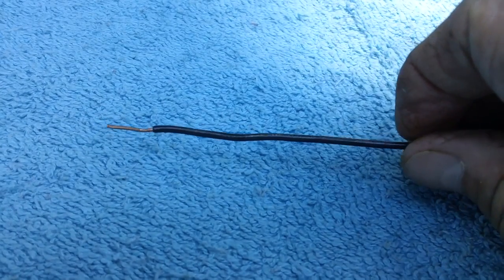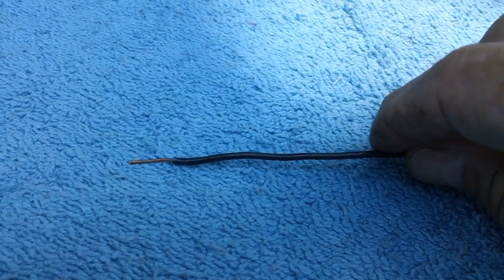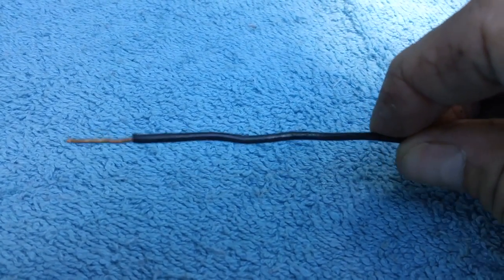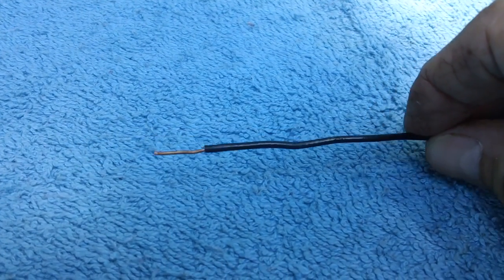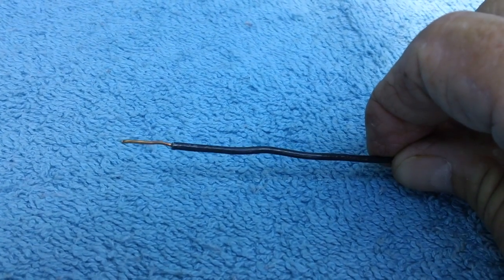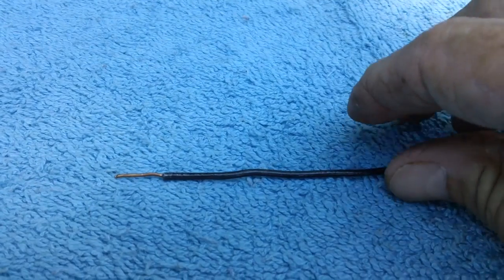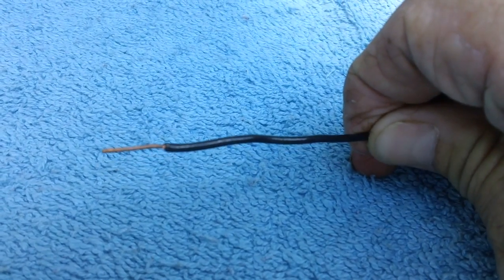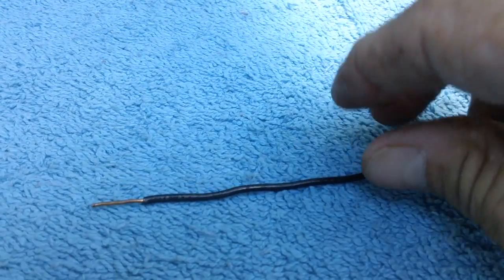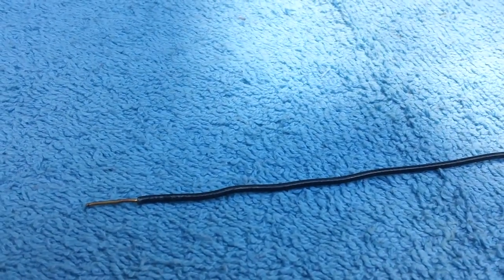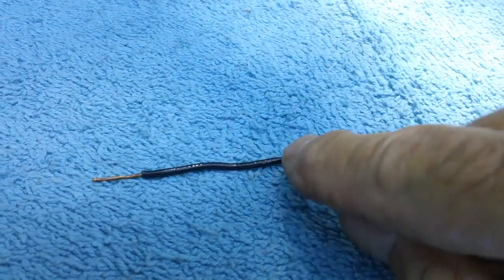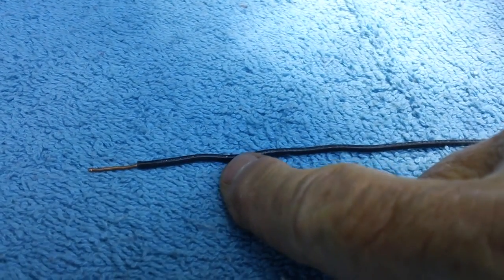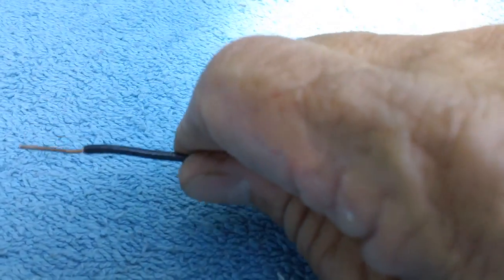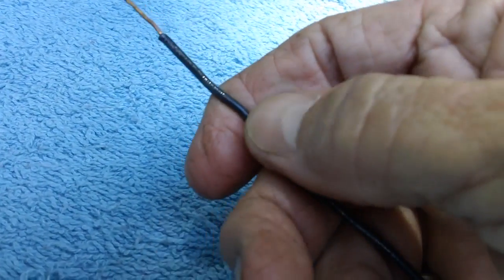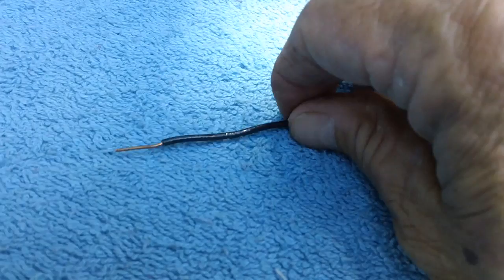The voltage limit of a piece of wire is determined by the type of insulation on it, the quality of the insulation, and the thickness of that insulation. If you have very thin insulation, the voltage rating comes down. If it exceeds the rating of the insulation, it will blow right through the side—it will melt it, blow right through the side. And if you're holding the wire like that, it's going to blow into your hand. Simple as that. Everybody knows that now.